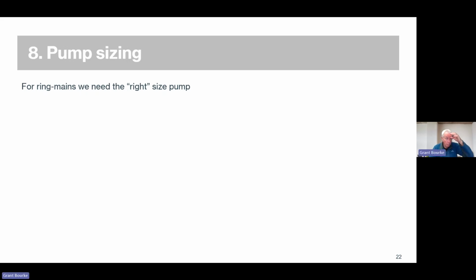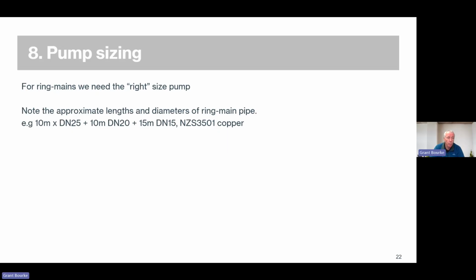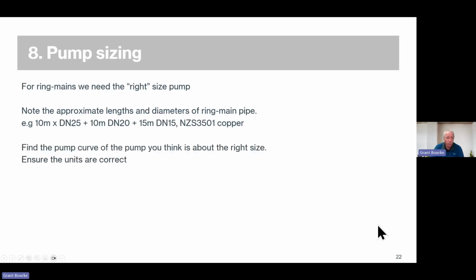Right, let's have a look at this ring main pump. So we need the right size of pump. Bigger is not better, and you'll see why in a minute. What we're going to go through is a worked example where we've got a modest sort of single level place, and we've ended up with about 10 metres of 25 mil, another 10, reducing to another 10 metres of 20 mil, and going down to some 15 mil plus the return, and it's all going to be in 3501 copper. Same principles apply to what I'm going to show you if you're doing it in other materials.